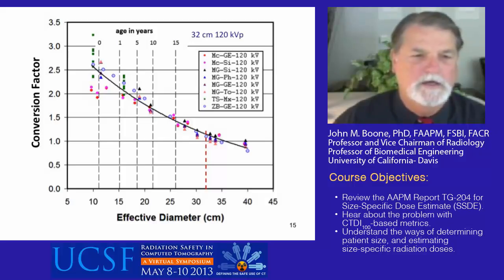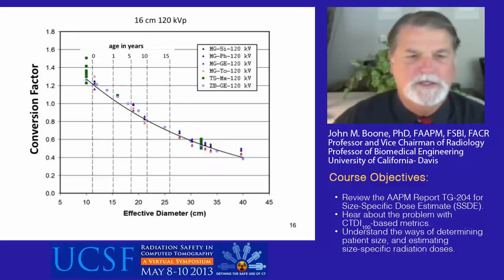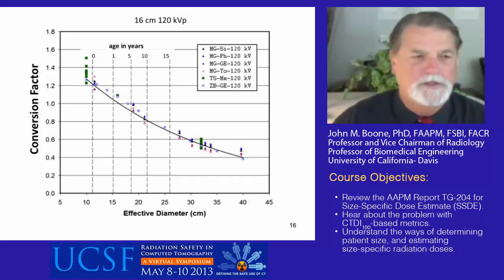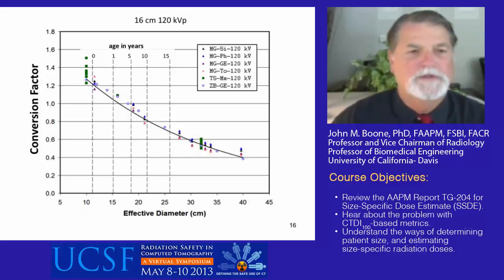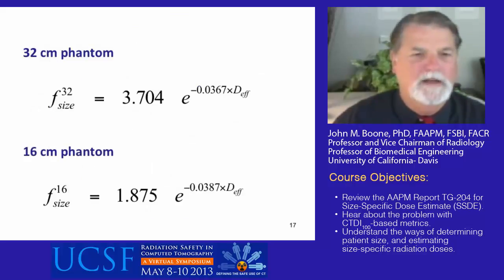For CT scanners using a 16-centimeter diameter PMMA phantom, the equivalent data shows the curve going through approximately unity at 16 centimeters. These two curves, for the 32-centimeter and 16-centimeter diameter phantoms, are well fit by an exponential function.